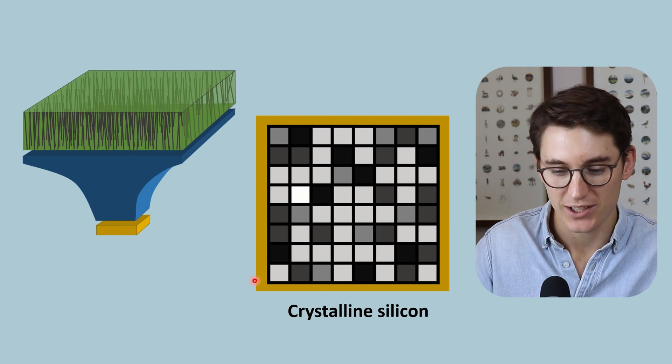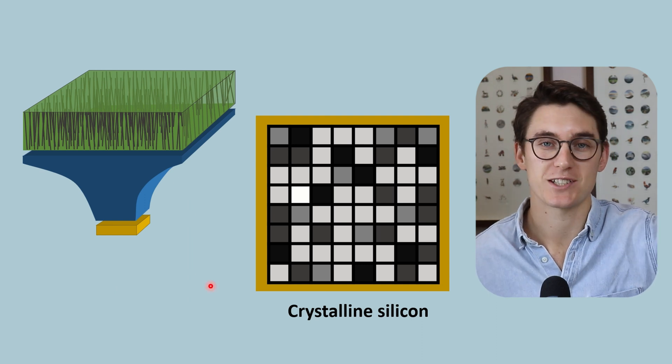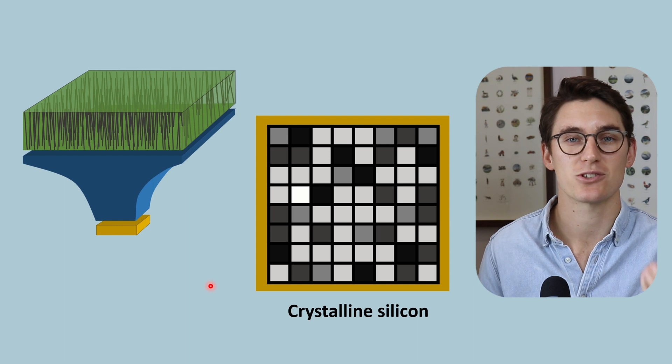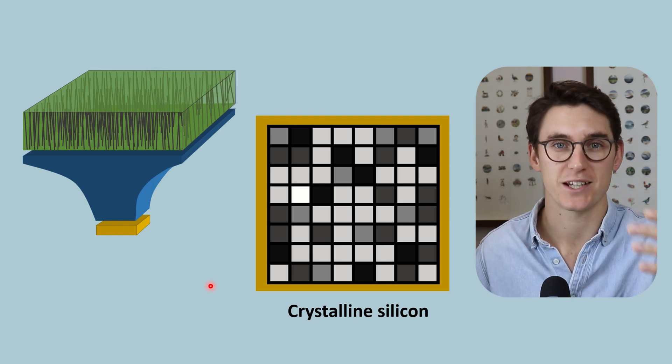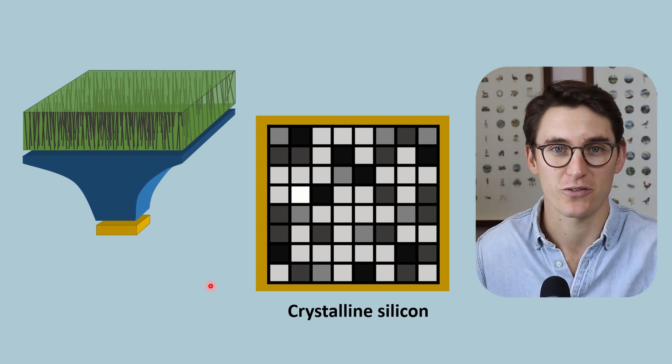Now when we want to read out these dexels, we can change the voltage along these voltage gates and allow those dexels to be released into what is known as an amplifier and then that signal can be digitized into a pixel value, a grayscale value that we can represent on our computer screen, ultimately making our radiograph that we've taken.